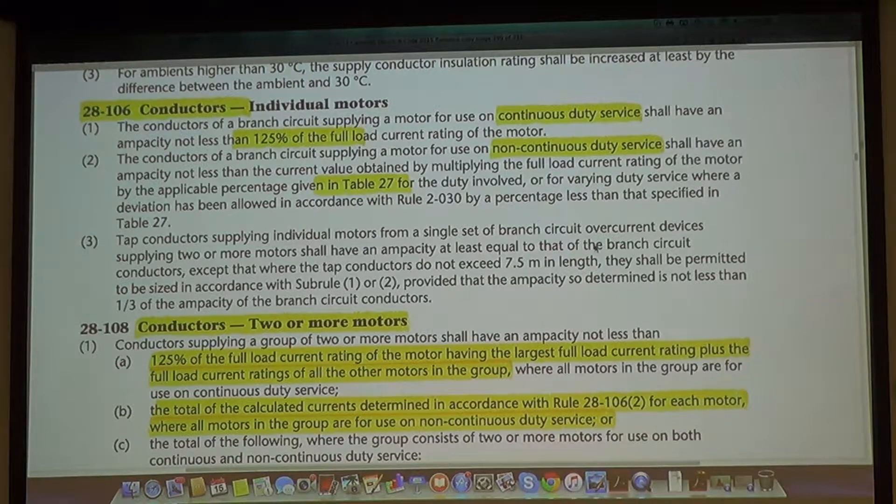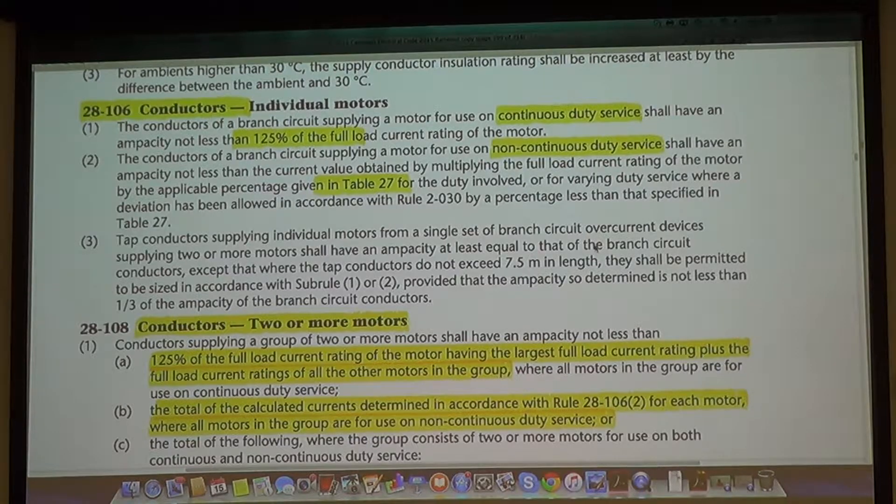For a non-continuous duty motor, what do I multiply it with? I go to table 27 to find the derating factor and multiply my FLA with the numbers on table 27.